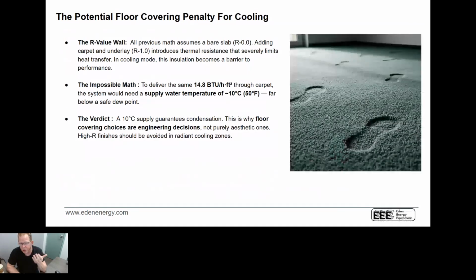Now, one of the challenges we have to be aware of is the math that I was talking about very quickly earlier about how many BTUs we can get into that floor. You got to remember that most floor coverings are not going to be just plain tile, right? You get into a situation where you've got a carpet that adds an R value. What was 11 BTUs per square foot could in fact become 15 BTUs per square foot. So we have to be really, really conscious that our supply temperature may have to adjust 10 degrees just to make up for the fact that there's a carpet on the floor.